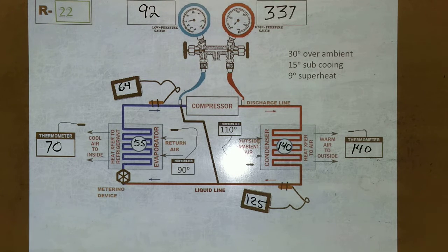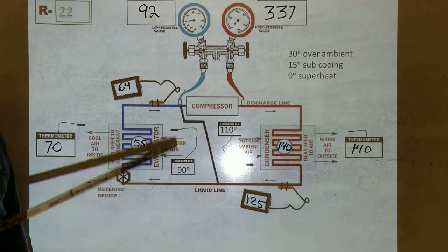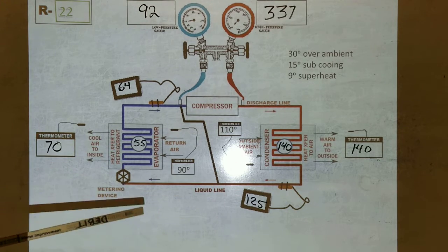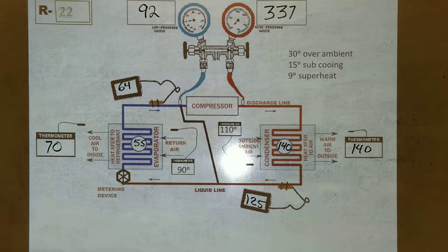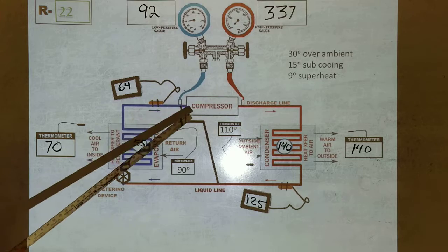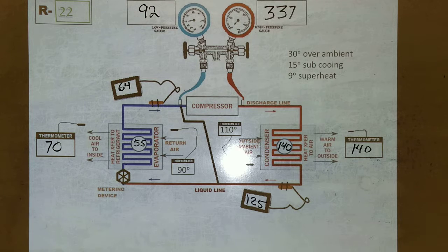If you also notice that we've taken a lot of readings on this system to find out exactly what's going on. So we're checking a system that's operating normally. You have to understand how the system works normally in order to troubleshoot any problems when it's abnormal, right? So we got a temperature here, here, there. We're taking a lot of readings.